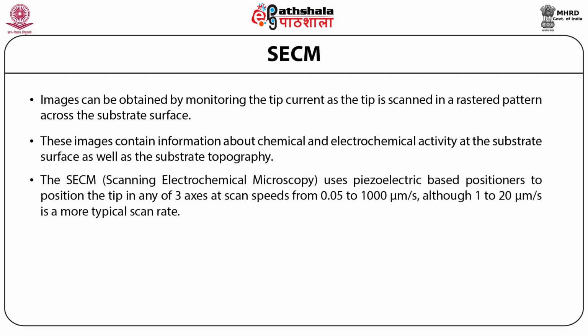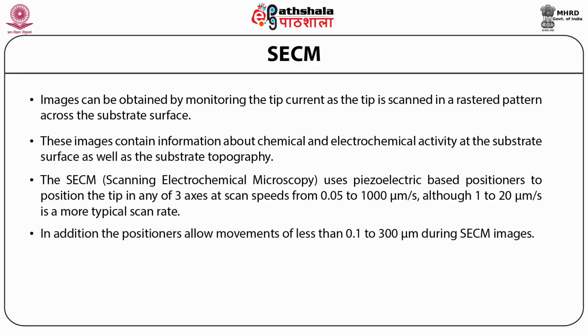The scanning electrochemical microscope uses piezoelectric-based positioners to position the tip in any of three axes at scan speeds from 0.05 to 1000 micrometers per second, although 1 to 20 micrometers per second is a more typical scan rate. In addition, the positioners allow movements of less than 0.1 to 300 micrometers during SECM imaging.